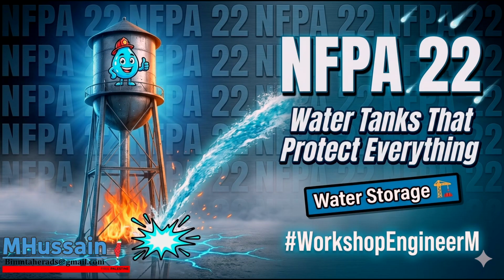Okay, that makes sense for the width, but what about the 6-inch height? Why not bolt it 2 inches off the floor to get every last drop of water, or maybe 24 inches off the floor to ensure a maximum flow area? It's a highly engineered balance of fluid dynamics. If you mount the plate 24 inches high, you create 2 feet of dead water below the plate. Because the pump is pulling from above the plate. Exactly. Once the water level drops to the top of the plate, the pump starts sucking air, rendering the remaining 2 feet of water completely unusable. In a massive tank, that could be tens of thousands of gallons of water wasted.